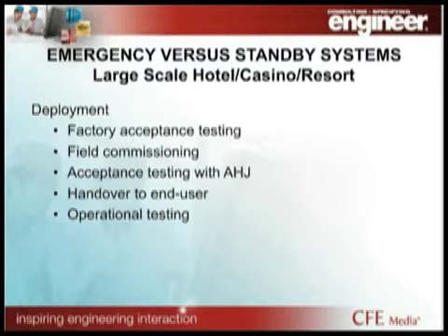And then the other thing is you've got to be ready for acceptance testing with the authority having jurisdiction. Depending on who that authority is, they're going to have different criteria. In Las Vegas, they'll hit a shunt button, drop the entire building into the black, and time to make sure that the emergency loads come on in 10 seconds or less. And then the handover is really important.